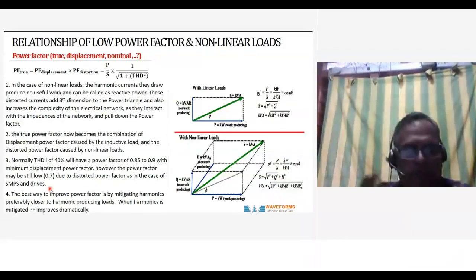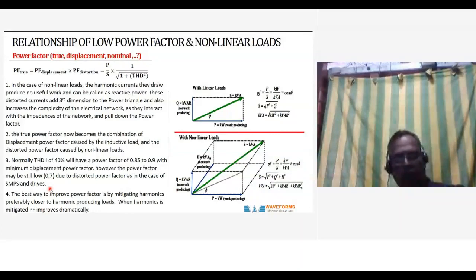Once you improve the distortion, or decrease the distortion level, the power factor improves automatically. So the best way to improve power factor is by mitigating harmonics, preferably closer to the harmonic-producing loads. When harmonics are mitigated, power factor improves dramatically. That is a very important statement. When harmonics are mitigated, power factor improves dramatically. Normally people try to solve it by installing some active filter. I'll tell you why that's not the ideal way. I'll come to that subject a little later.